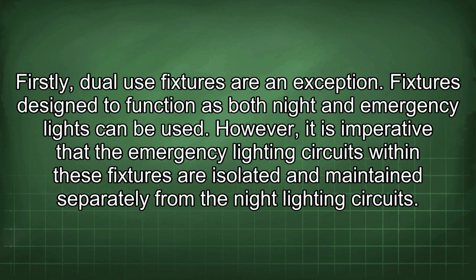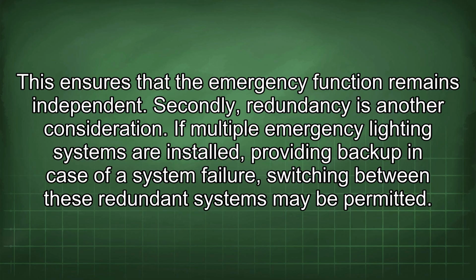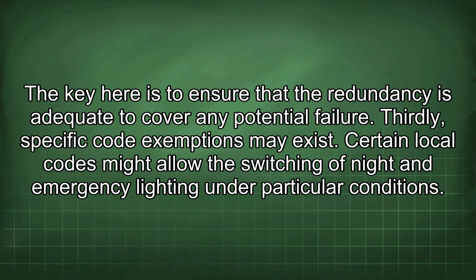Firstly, dual-use fixtures are an exception. Fixtures designed to function as both night and emergency lights can be used. However, it is imperative that the emergency lighting circuits within these fixtures are isolated and maintained separately from the night lighting circuits. This ensures that the emergency function remains independent. Secondly, redundancy is another consideration. If multiple emergency lighting systems are installed, providing backup in case of a system failure, switching between these redundant systems may be permitted. The key here is to ensure that the redundancy is adequate to cover any potential failure.